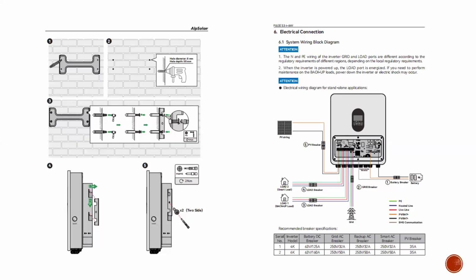And another thing that I want to point our attention to is the breaker specifications that are recommended for this system. For a 6 kilowatt system, you need a battery breaker of 160 amps, a 63 volts 160 amp breaker, because the maximum discharge current of this unit is 135 amps. So nowhere in the world is it going to get to a point whereby it's going to discharge 250 amps from the battery. Using a 250 amps breaker for a 6 kilowatt inverter is just a sheer waste of resources, and of course it costs more, and it's not going to be effective for what it is designed for. So a 160 amps breaker is what you need.